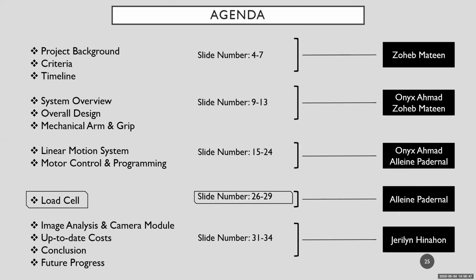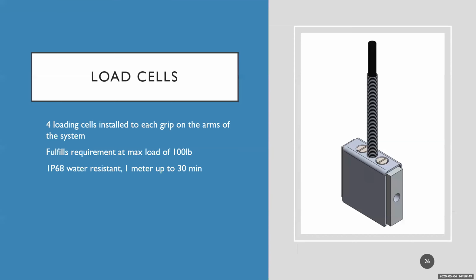Now I will be talking about load cells. As mentioned earlier, there will be 4 load cells installed to each grip on the linear rail system. The selected load cell fulfills the requirement of a maximum load of 100 pounds, about 445 Newtons. It has a rating of IP68, meaning it is waterproof and can be submerged up to 1 meter for about 30 minutes.